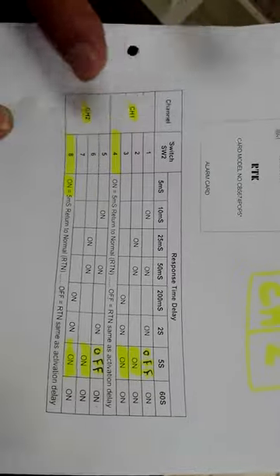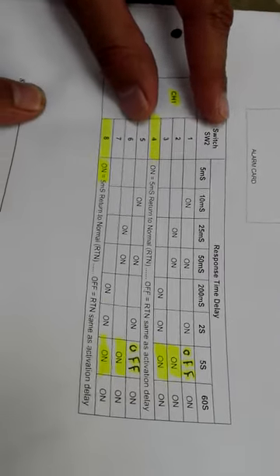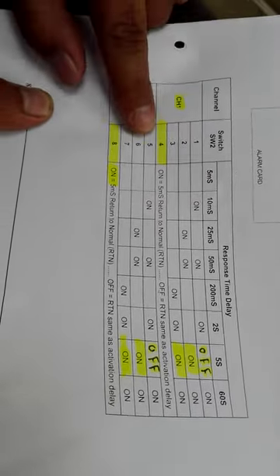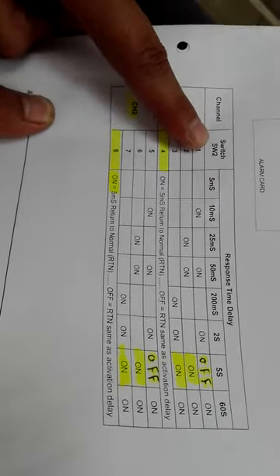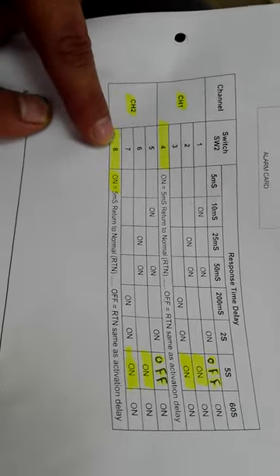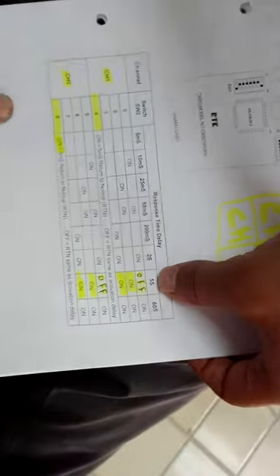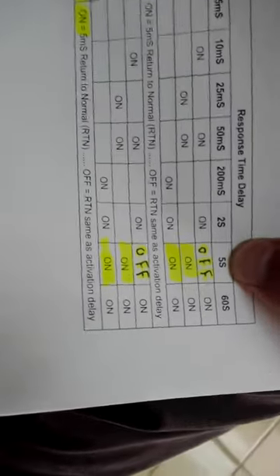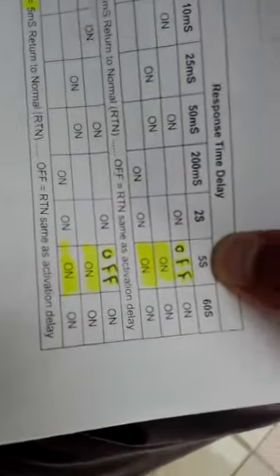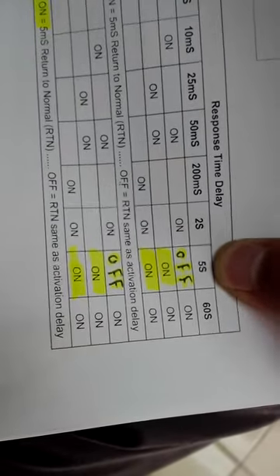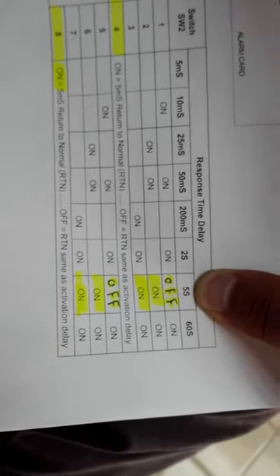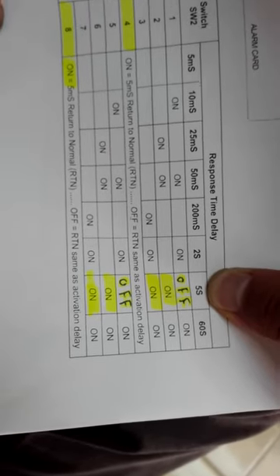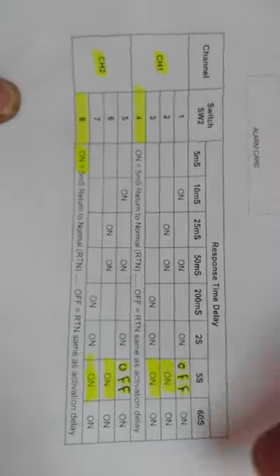For channel 1, switch 2 has 4 switches: 1, 2, 3 and 4. For channel 2, switch 2 has 5, 6, 7 and 8. Now for our ABC panel, according to our requirements, we need a 5 second response time delay. So we have to make changes in switch SW2 in this pattern.